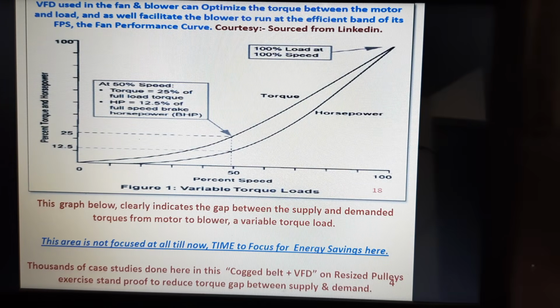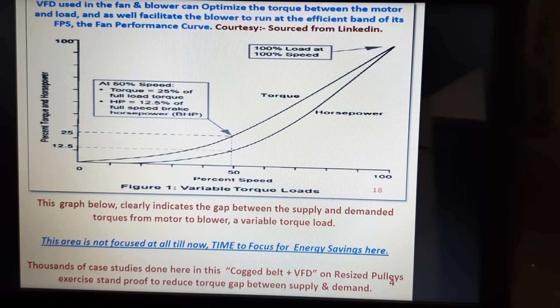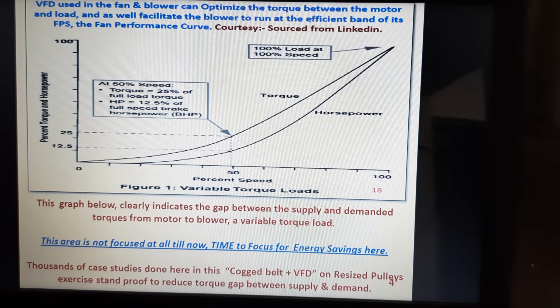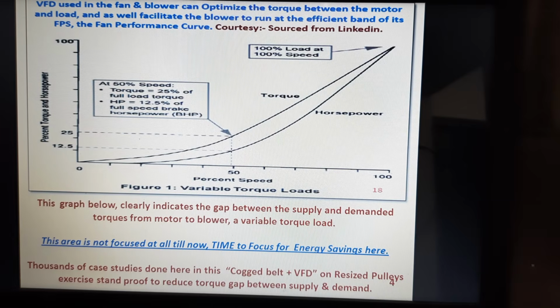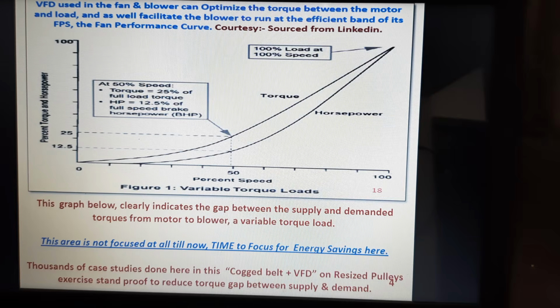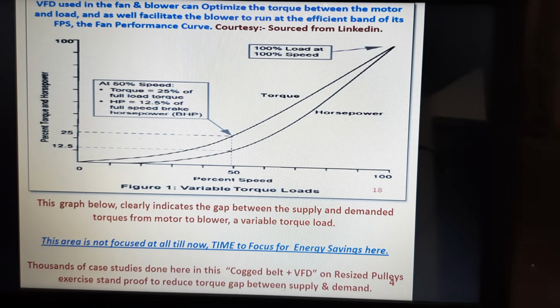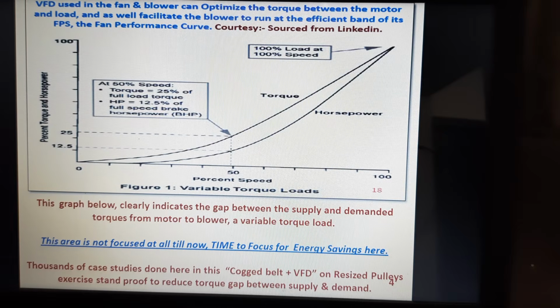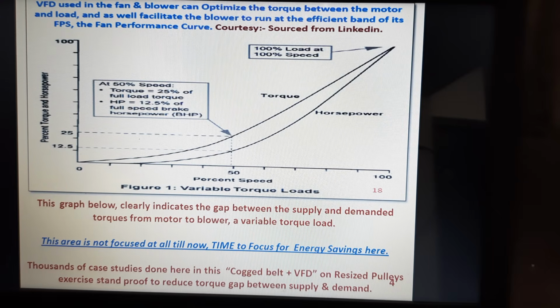Elaborating more on variable torque loads, a VFD needs to be used for a variable torque load such as a blower or fan. The VFDs used in the blower and fan can optimize the torque between the motor and the load and also facilitate the blower to run at an efficient band of its fan performance curve. The image, sourced from LinkedIn, clearly shows that at 100% of the load, the torque is 100% and the speed is also 100%. Whereas at 50% of the speed, the torque is only 25% of the full load torque and the HP is only 12.5% of the full load brake horsepower of the blower. This graph indicates clearly the gap between the supply and the demanded torque from the motor to the blower. Basically, the blower is a variable torque load which we are trying to utilize here.